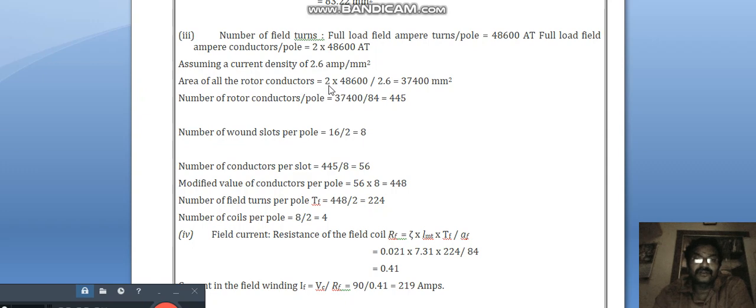Area of rotor conductor is equal to 2 into 48,600 divided by 2.6, we will get 37,400 square millimeter. Number of rotor conductors per pole is equal to 37,400 divided by 84, 445. Number of wound slots per pole is equal to 16 / 2 is equal to 8. Number of conductors per slot is equal to 445 / 8. That value would be 56.